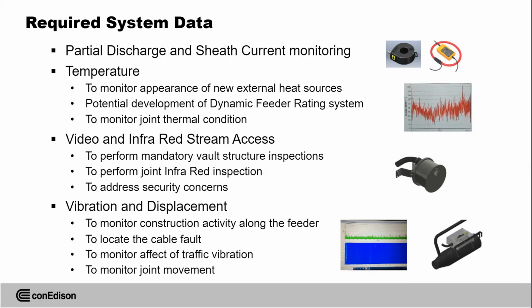So that's why we install a single point bonding system. But we need to understand: is it really no shielding current here, or does some current occur, especially if you use a cross bonding system or anything else? So a sheath current monitoring system, absolutely not expensive, a very simple system, can prevent a much more significant event, when you can have an overheated cable because of significant current in the shielding.